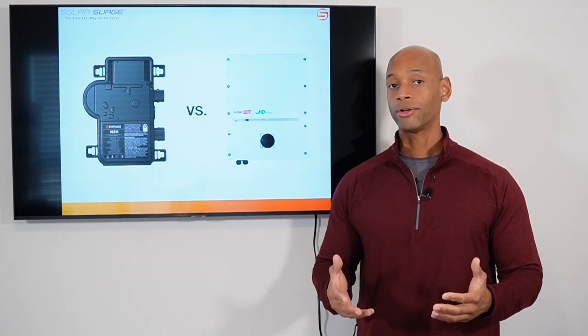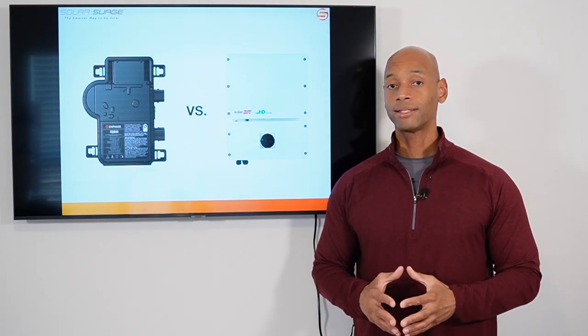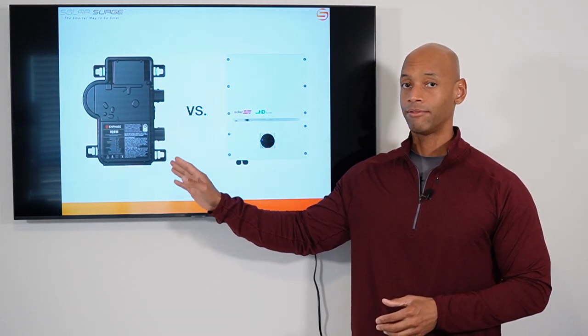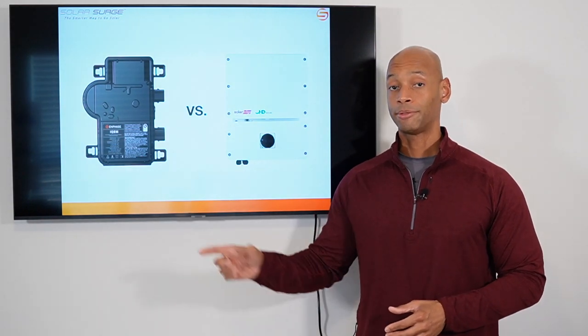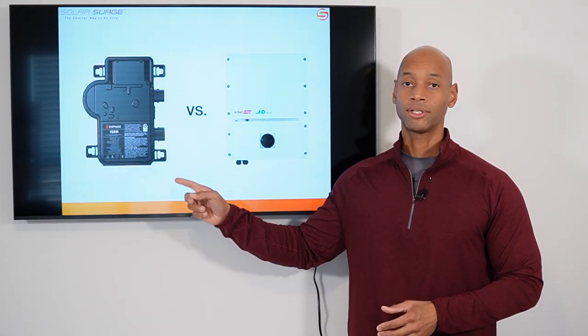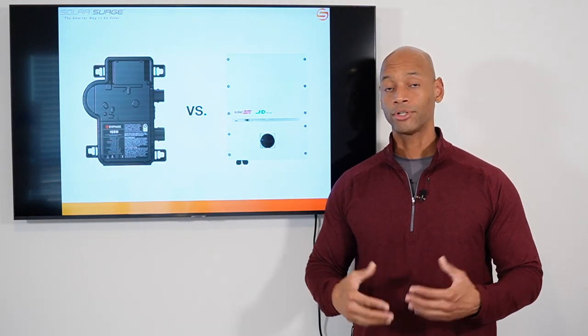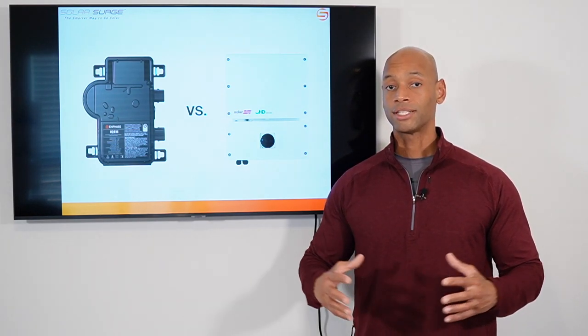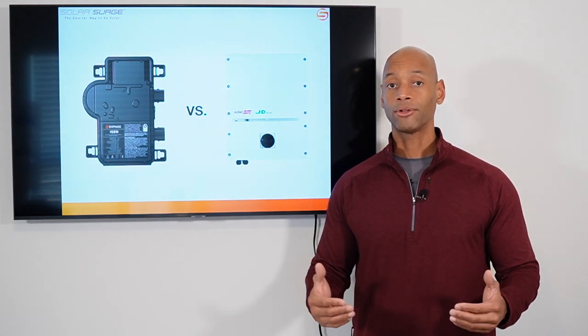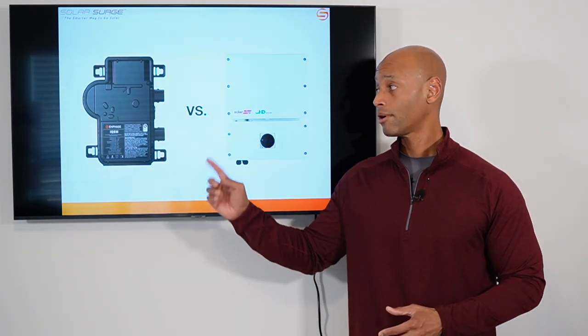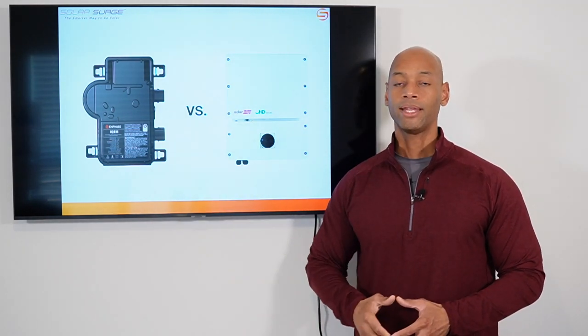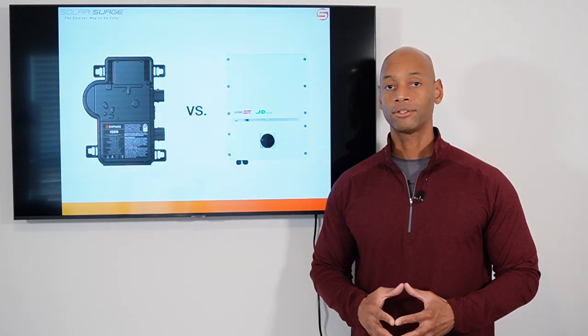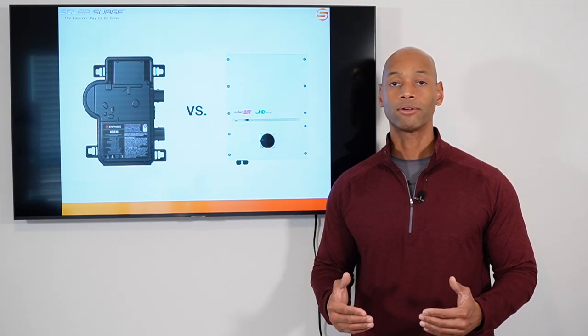Now when you go to size the inverter for your solar system, you're going to want to take a look at the difference in the solar panel power rating and the inverter power rating. And this is especially important when you're looking at microinverter systems. Because what we've seen in the past year, as we're now talking about going into 2023, is that the size and the power output of the solar panels themselves has been outpacing the growth in the power output on the microinverters.